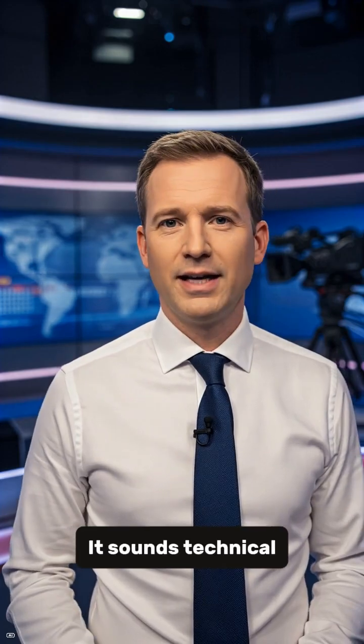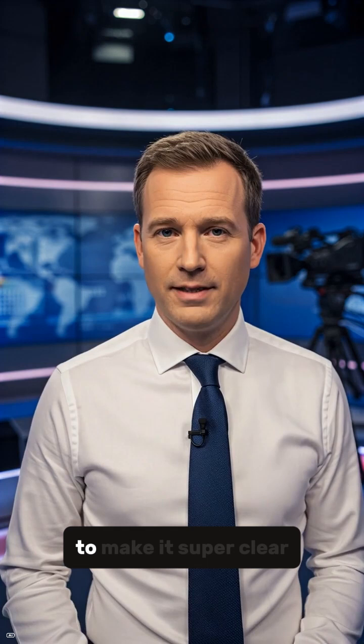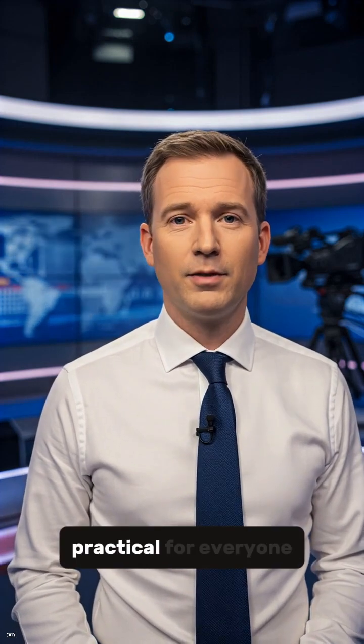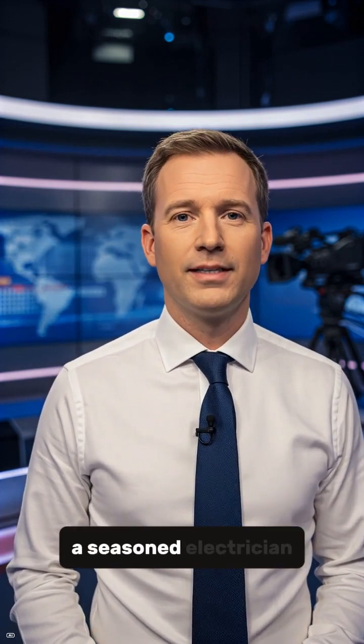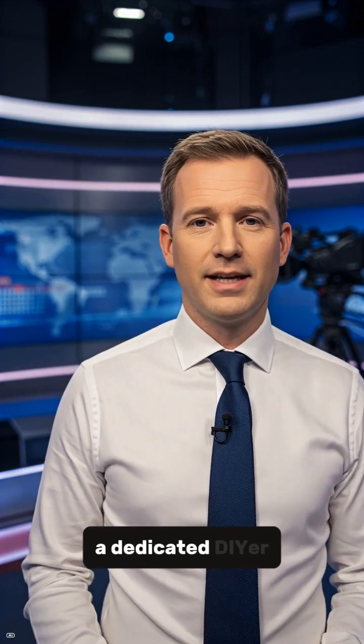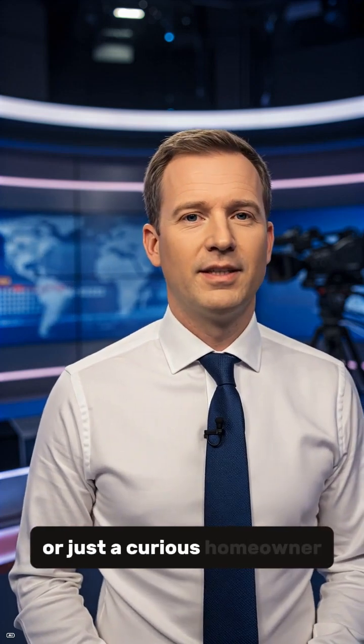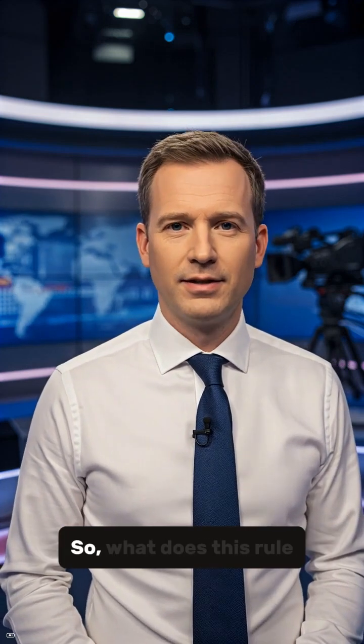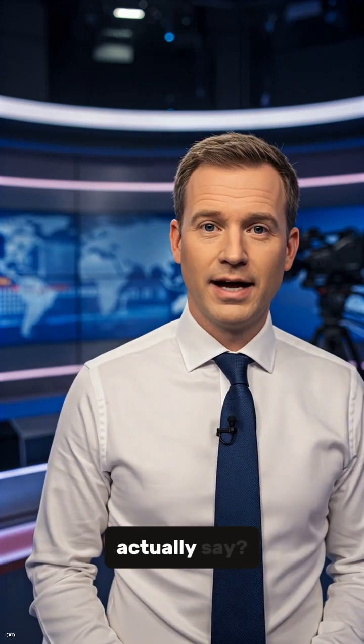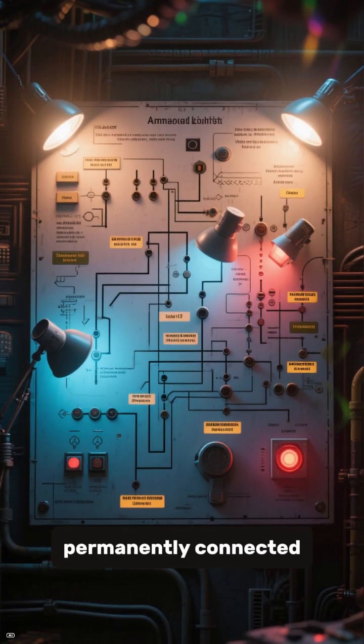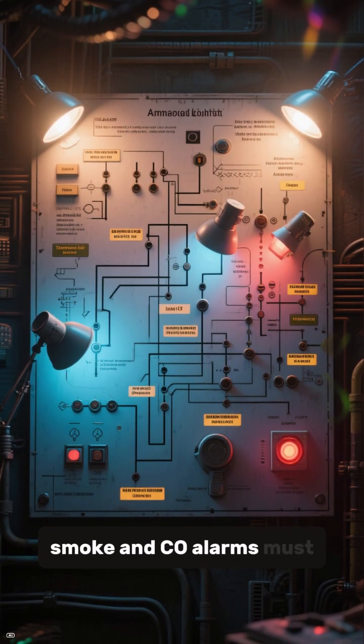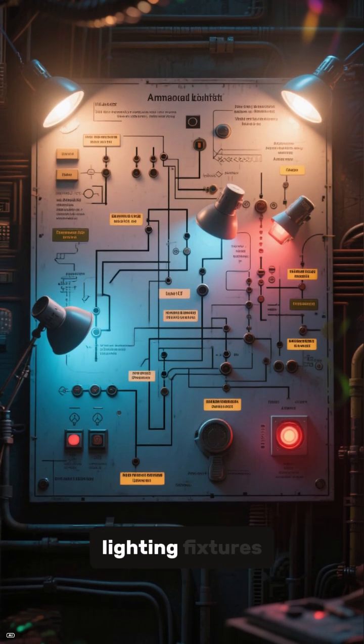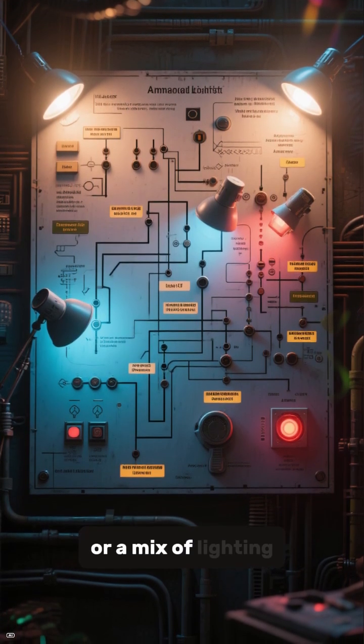It sounds technical, but I promise to make it super clear and practical for everyone, whether you're a seasoned electrician, a dedicated DIYer, or just a curious homeowner. So, what does this rule actually say? It states that permanently connected smoke and CO alarms must be supplied from a circuit that also powers either lighting fixtures or a mix of lighting and receptacles.